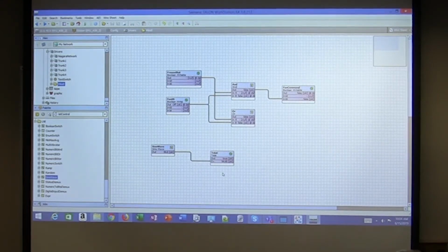So when's he supposed to turn off? When it gets below the deadband. So when he gets below 40, because we had a set point of 50, and I put 20 in there for the deadband, so I got 10 above and 10 below. So once this gets back up to 60, boink, he's going to turn back on and go true. Okay? So I can use this to kind of simulate some numbers for me if I wanted to.